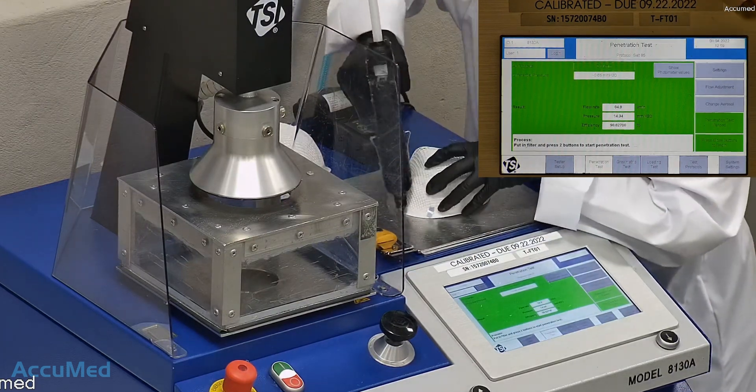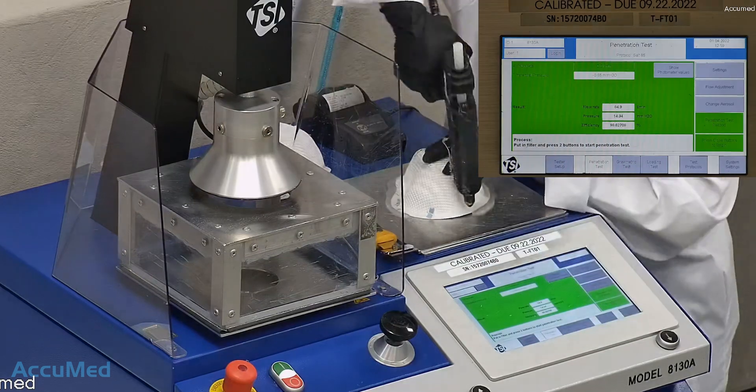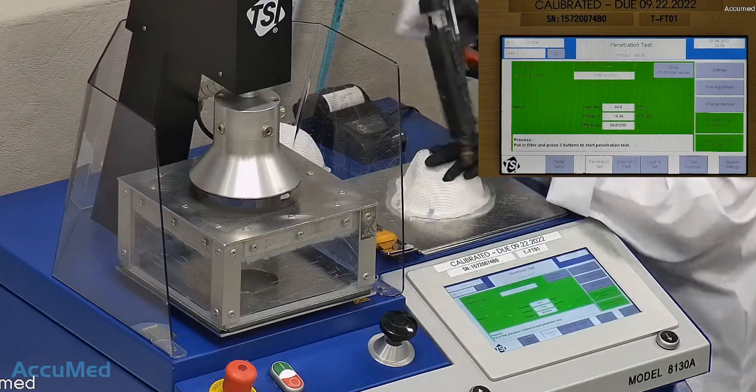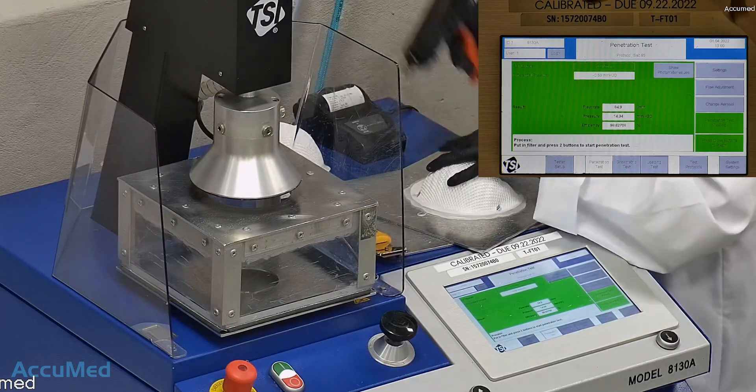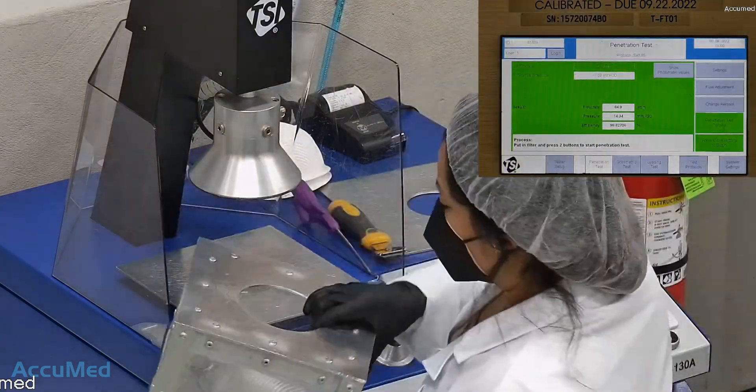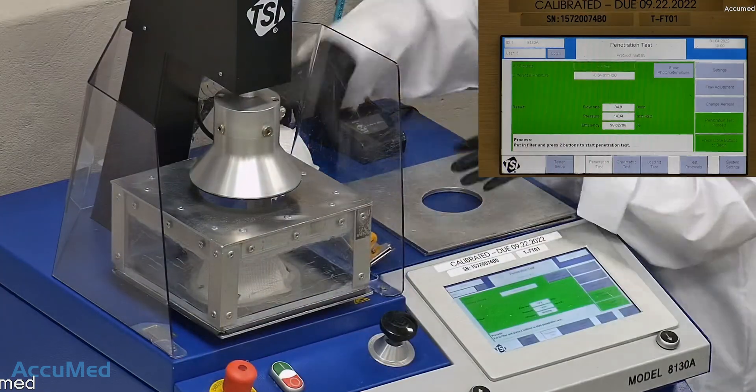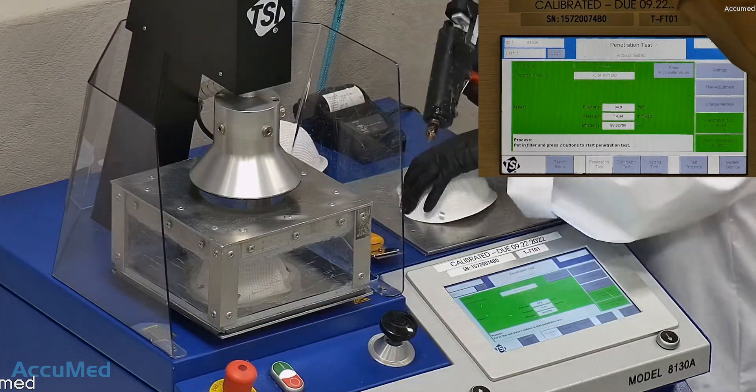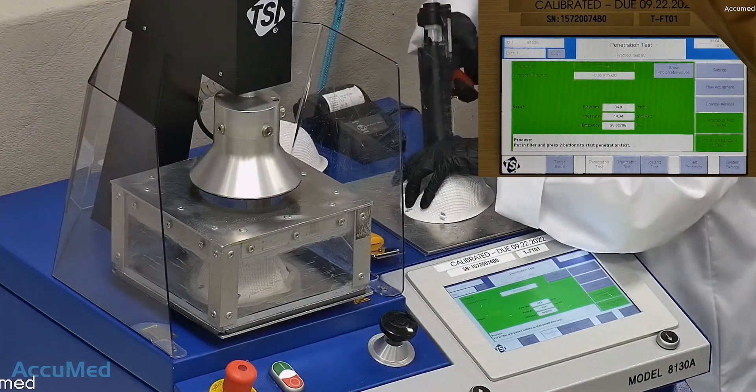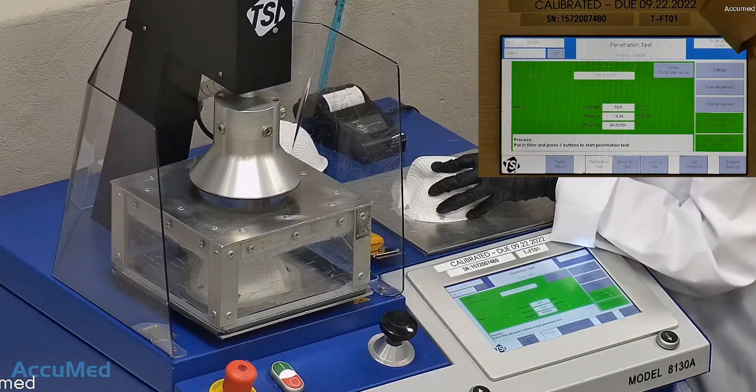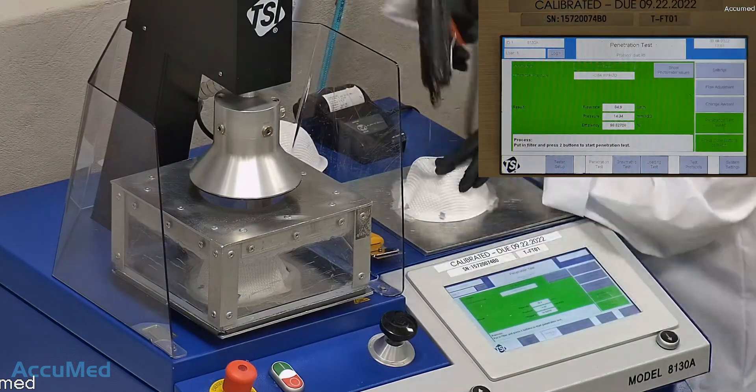We first run a tester setup and start removing the headband from the respirator before placing it onto the testing plate to ensure a proper seal. Then we make sure that the mask is properly and completely sealed with hot glue to the testing plate. When applying the hot melt glue, we make sure that there is no holes or leakage around the seal to ensure accurate results. The testing plate is then attached to the frame and the box is placed under the TSI filter holder for testing.